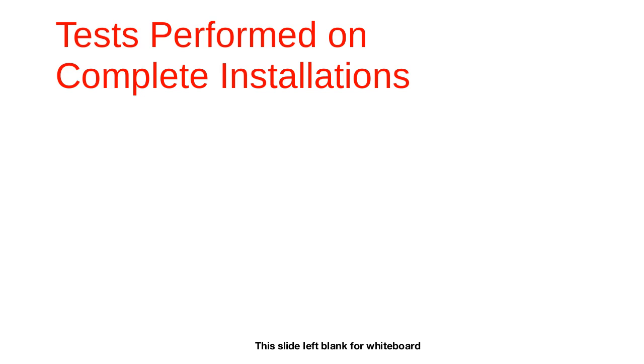So in this test, we have said there are a number of tests that can be conducted on an installation, depending on whether it's dead or live. Under dead installation, we have the continuity and ring tests, and under that we have the insulation resistance. I repeat, in a dead installation, we have the continuity test plus the ring test, and also the insulation resistance test.